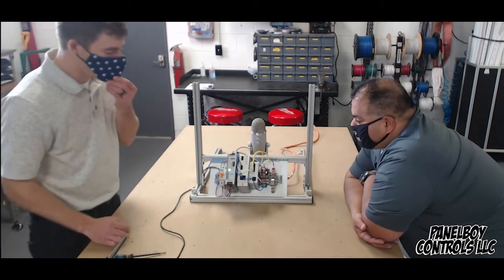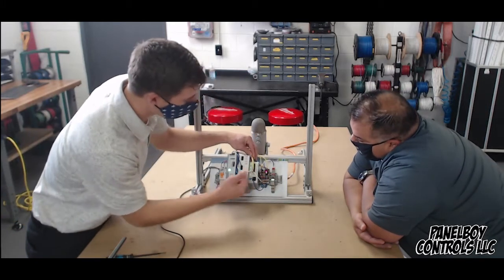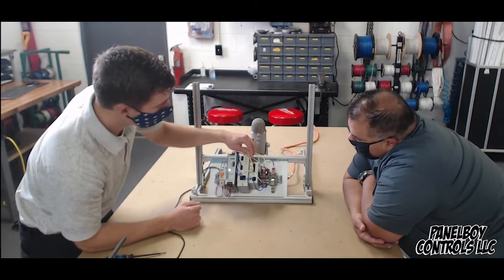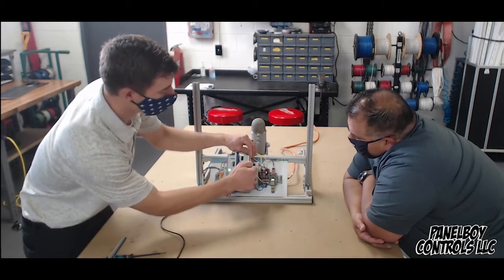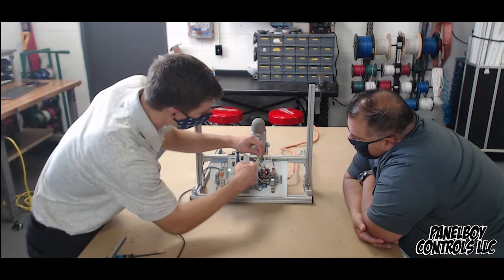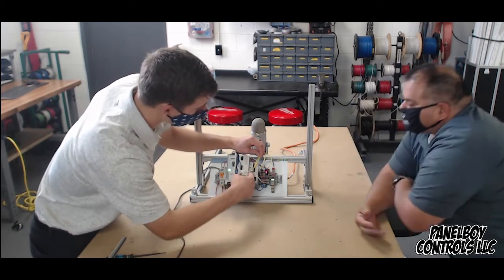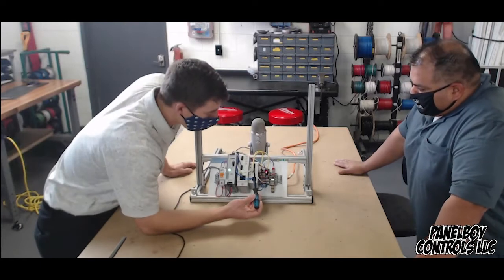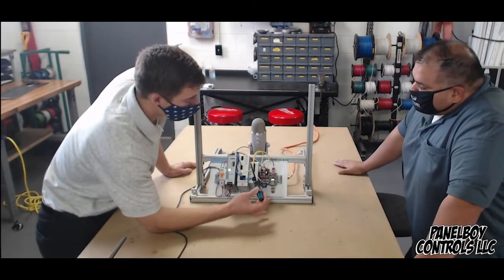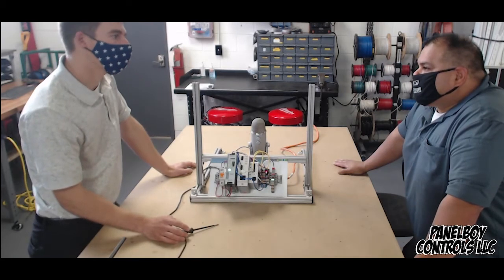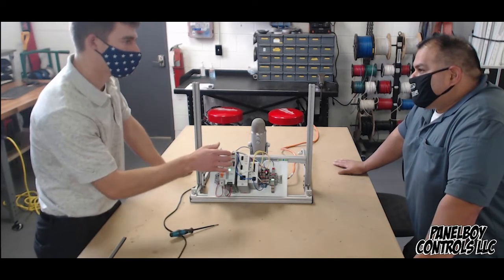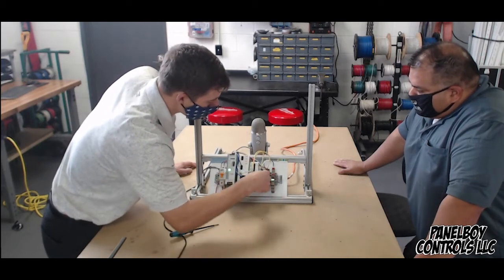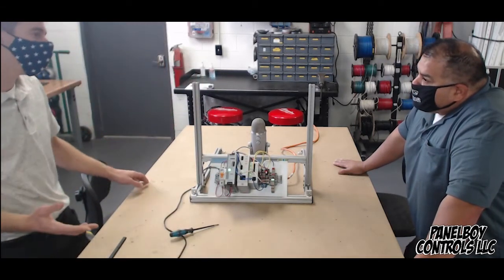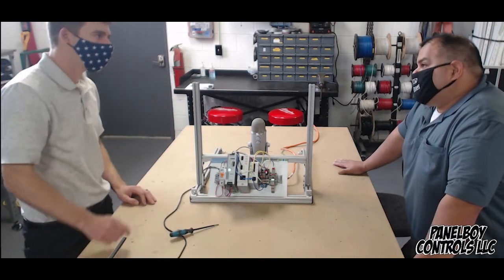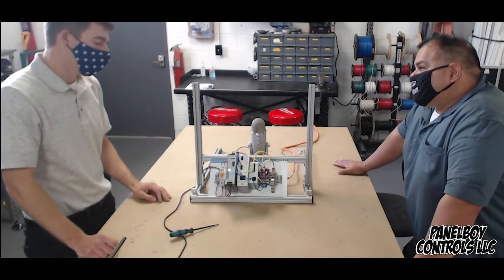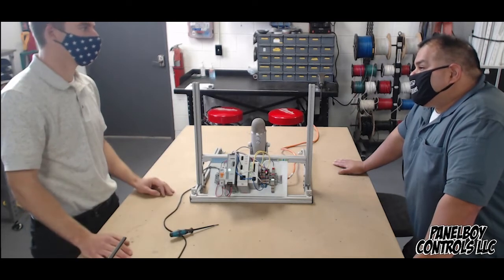To proceed with the demo, you see four LED indicators for each channel. The four first termination points are your protected circuits. I'm turning them off just by pressing the button here. One of the things we did when we redesigned the circuit breaker module was make it harder for someone to walk up and mess with the settings, because maybe you're having trips or something you need to fix in your machine, and you don't want someone cranking up the actual load this thing is set to. That could make a motor blow.